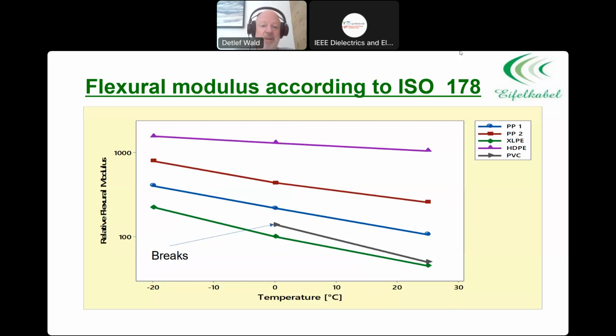So what's up here is the low line, the green one is XLPE, and then you have different polypropylene compounds, the blue and the red. I hope you have the same colors that I have. And on the top there is a high density polyethylene commercial jacketing compound. The flexibility is measured according to ISO around that temperature range. And we also used as a comparison the PVC jacketing compound. And as you can see, we couldn't measure it at -20 degrees because it breaks at lower temperature.